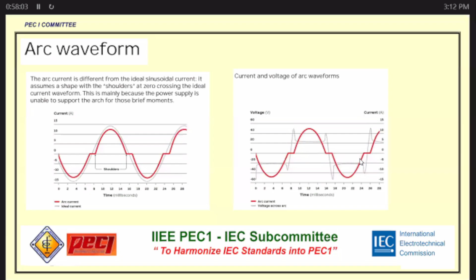That is how the arc fault detection device detects the presence of an arc fault in the system, which an ordinary miniature circuit breaker cannot detect. Imagine, the current is so small, but it distorts the sinusoidal waveform — that's for both current and voltage.